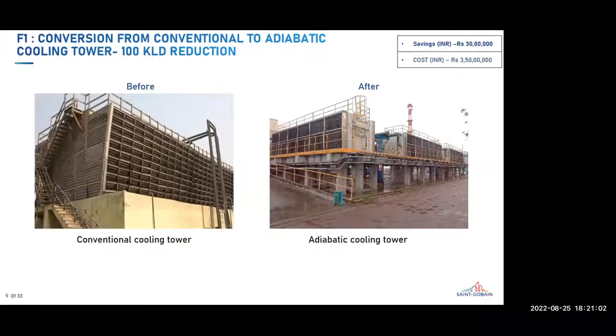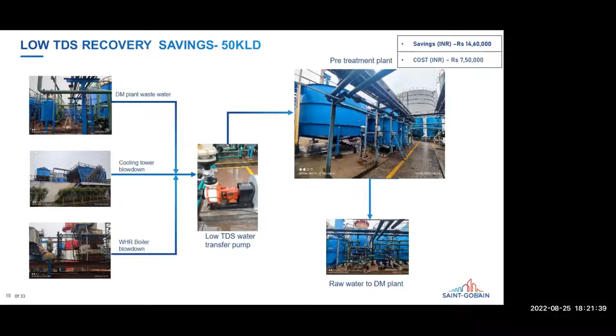This is one of the major projects which we have done in our plant: low TDS recovery. The savings is around 50 KLD. We collect all the wastewater from our DM plant, cooling tower, and WHR Boiler blowdown water into a common sump. From there, we pump it using transfer pumps to the pre-treatment plant, where we remove suspended solids and turbidity. We then use the same water again as raw water for our DM plant. The total investment of this project is around 7.5 lakhs, and there are savings as well.